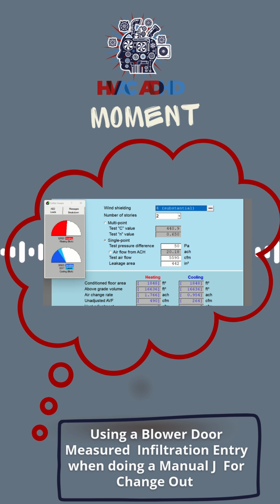If we want to do heat pumps, we're probably going to do two heat pumps, because you can't get a much bigger heat pump, especially an inverter cold weather heat pump, than 48,000 BTUs in most brands right now. And then you look at your cooling load here. What happened to your cooling load? Well, the sensible cooling didn't go up all that much, but look at your latent load. You now have double the amount of water to worry about, and that is going to be a problem finding an inverter heat pump, really any heat pump at this tonnage, that can handle that latent load.